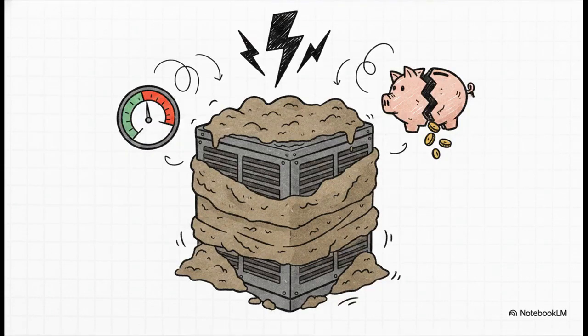And trying to breathe through that heavy blanket of dirt causes some pretty severe mechanical symptoms. Your head pressure, which is how hard the system has to literally push to circulate refrigerant, spikes drastically. Because of that, your compressor amperage rises and your energy consumption absolutely soars, while your overall cooling capacity just drops off a cliff. The equipment might still be running and making noise, sure, but it's incredibly inefficient and you're drastically shortening the life of your expensive compressor. Seriously, a relatively simple cleaning routine with a garden hose can prevent a massive repair bill here.